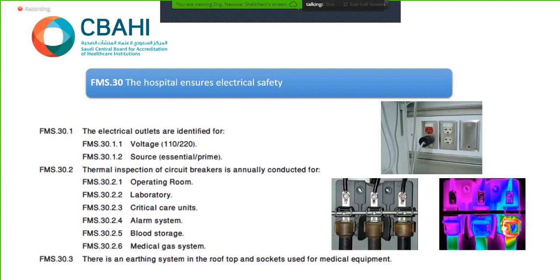Earthing system -- we may have talked about it yesterday. Earthing system should be available, and can be proven one of two ways: either the biomedical engineer measures the resistance between the outlet and the equipment, which to the best of my knowledge should not exceed 0.2 ohm, or the maintenance people can prove it if they have a well for earthing full of gravel and coal.